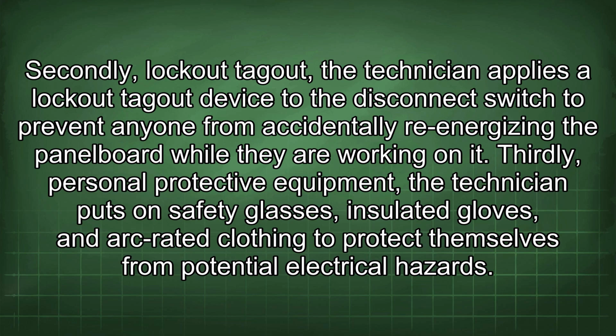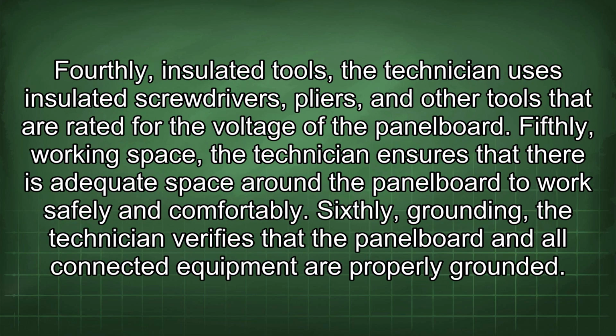Thirdly, personal protective equipment. The technician puts on safety glasses, insulated gloves, and arc-rated clothing to protect themselves from potential electrical hazards. Fourthly, insulated tools. The technician uses insulated screwdrivers, pliers, and other tools that are rated for the voltage of the panel board. Fifthly, working space. The technician ensures that there is adequate space around the panel board to work safely and comfortably. Sixthly, grounding. The technician verifies that the panel board and all connected equipment are properly grounded.